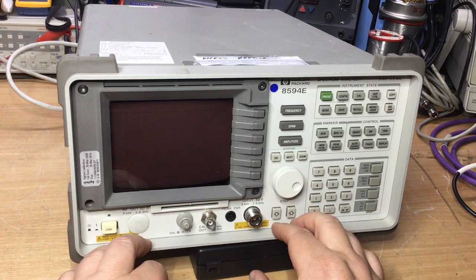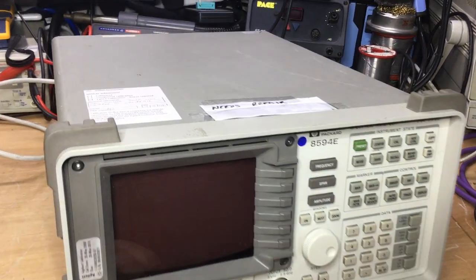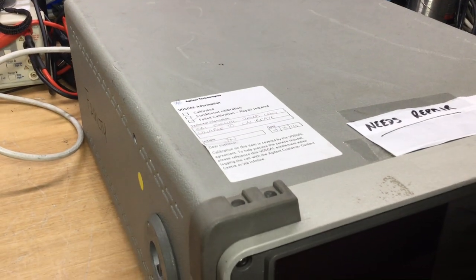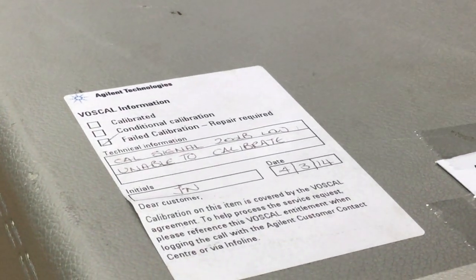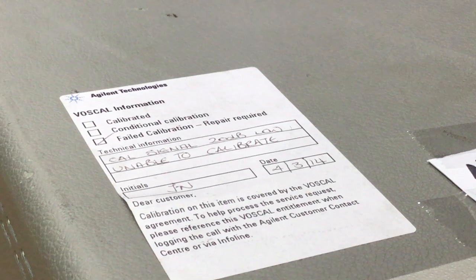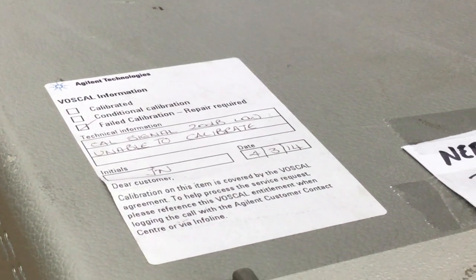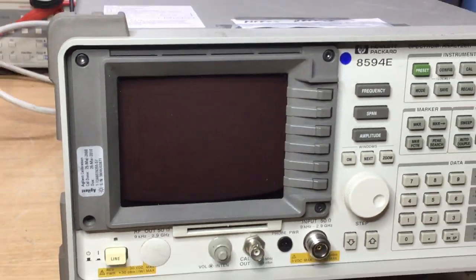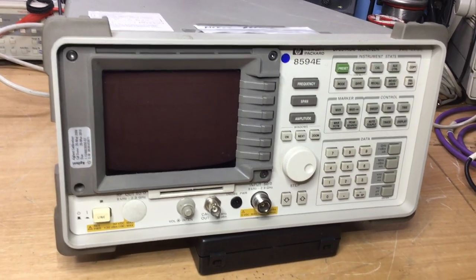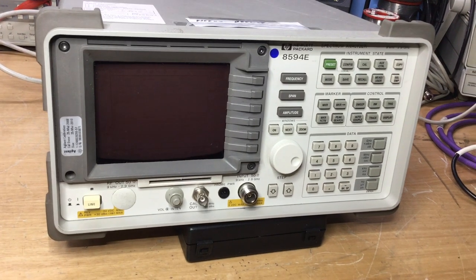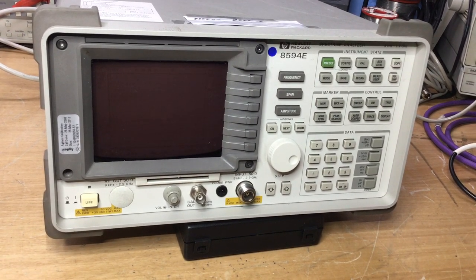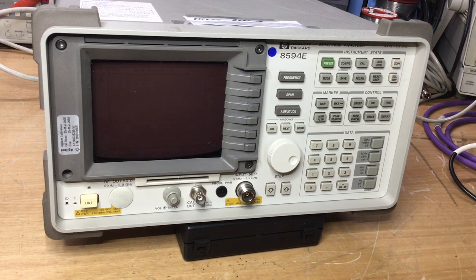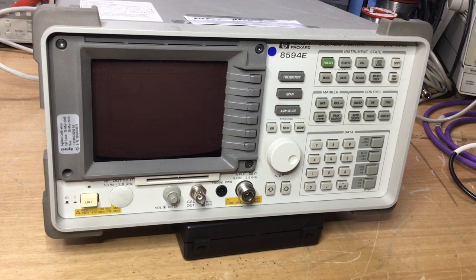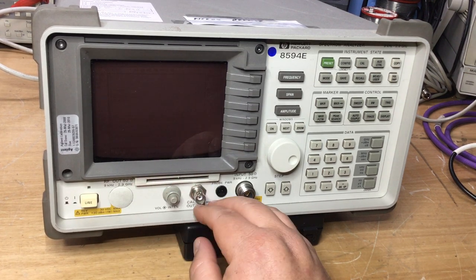Now this instrument has been previously looked at by HP Agilent themselves, and on the top here we've got fault information, which tells us that it won't calibrate. It says cal signal 20 dB low, unable to calibrate, and that was back in 2014 by Agilent Technologies. So obviously it's been looked at, but it just needs another look to verify what the fault is, because the HP Agilent ticket on the top doesn't say what it suspects to be faulty within the unit, what board or what module. So we'll need to look at that.